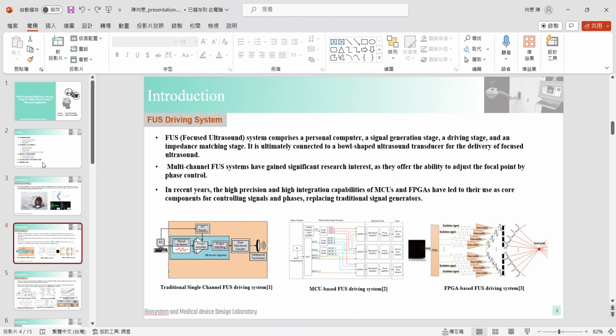A FUS system can be divided into four main components: a computer interface, a signal generator, a driving unit, and an impedance matching unit. The system is connected to a concave ultrasound transducer for focusing. While single-channel FUS systems are prevalent in the market, recent research suggests that multi-channel phase control offers enhanced flexibility by allowing control of the focal point and depth. However, as the number of channels increases, system volume and complexity become significant challenges.